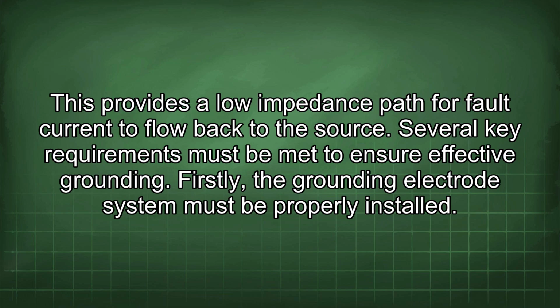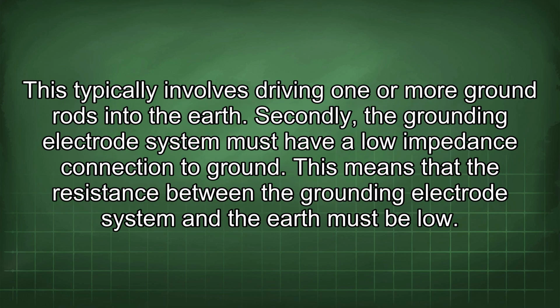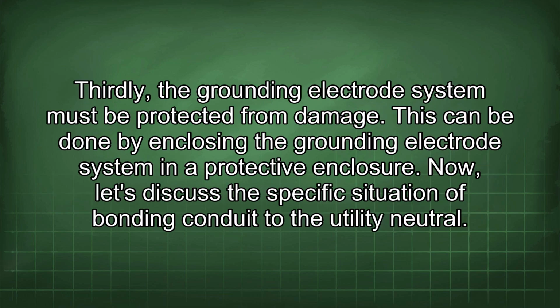Several key requirements must be met to ensure effective grounding. Firstly, the grounding electrode system must be properly installed. This typically involves driving one or more ground rods into the earth. Secondly, the grounding electrode system must have a low impedance connection to ground. This means that the resistance between the grounding electrode system and the earth must be low. Thirdly, the grounding electrode system must be protected from damage. This can be done by enclosing the grounding electrode system in a protective enclosure.